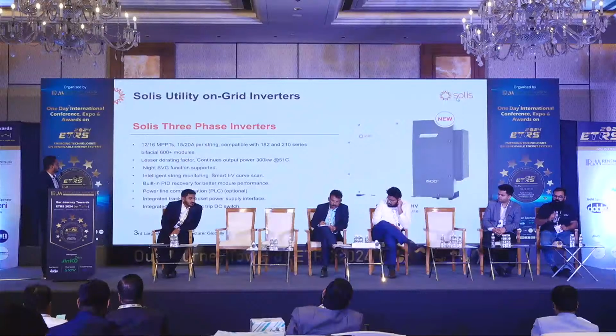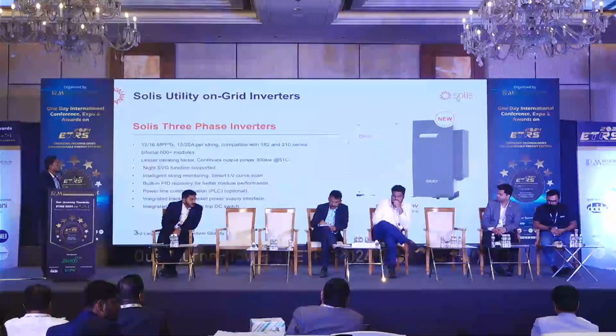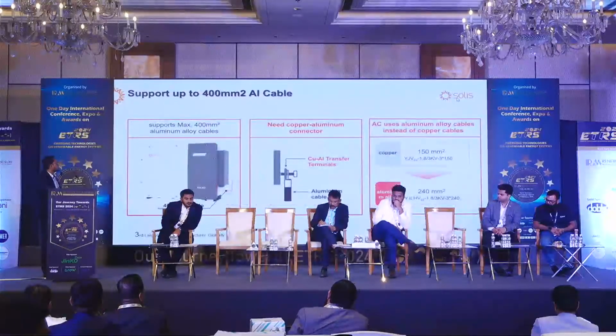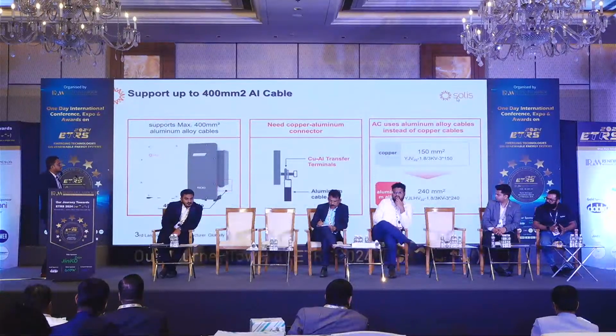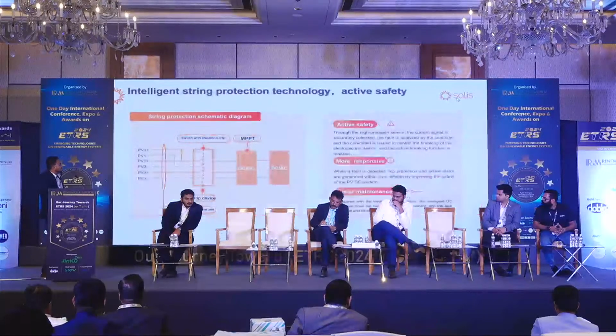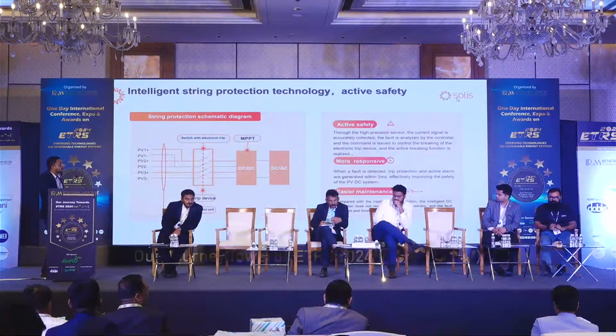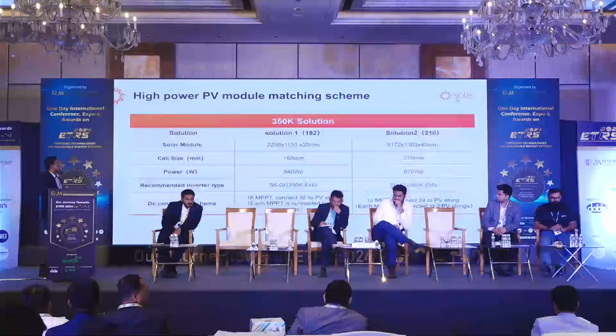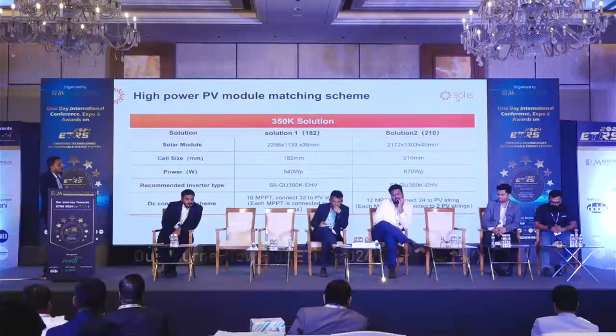And again, it supports night SVG functions, PLC, and we are giving an electronic trip DC switch to protect from DC side short circuit. It supports a maximum of 400 square mm aluminum cables in AC side termination. And we are giving a trip type DC switch, electronic trip. It trips automatically when any short circuit happens on the DC side. It supports 182 and 210 wafer or cell modules also.